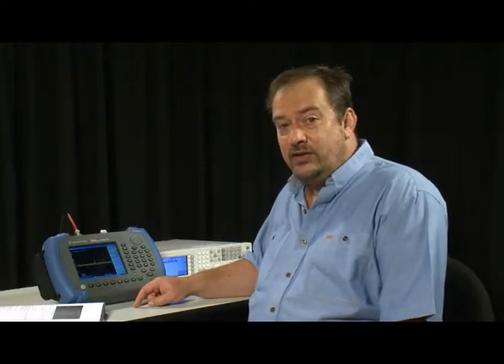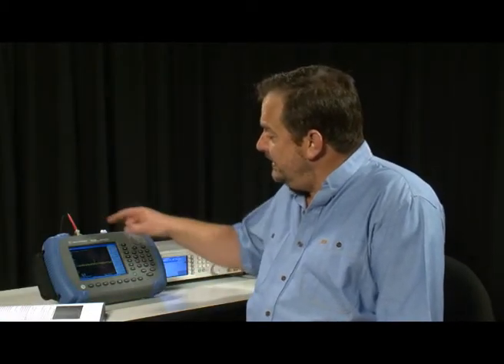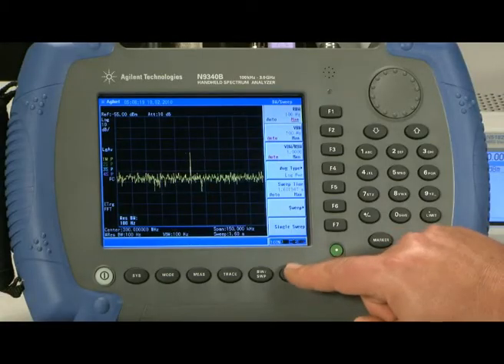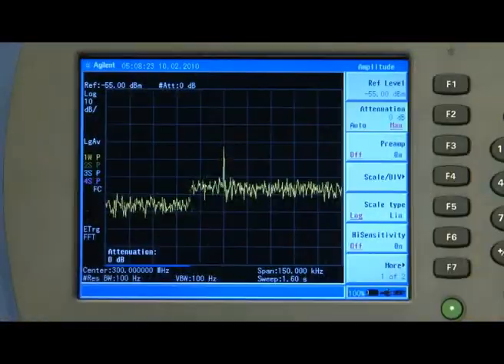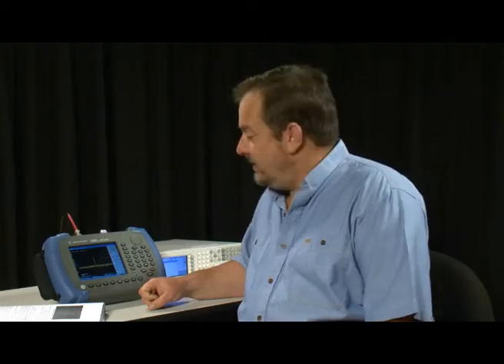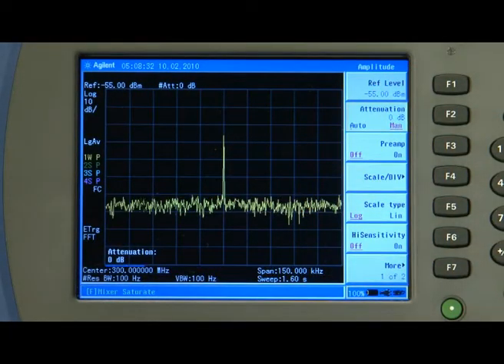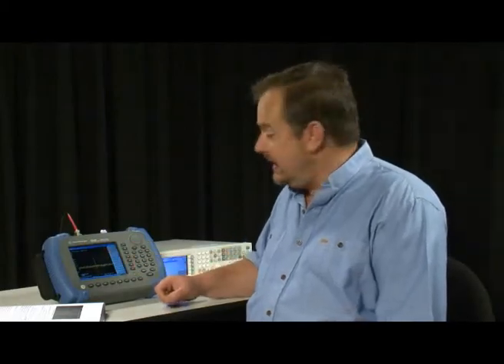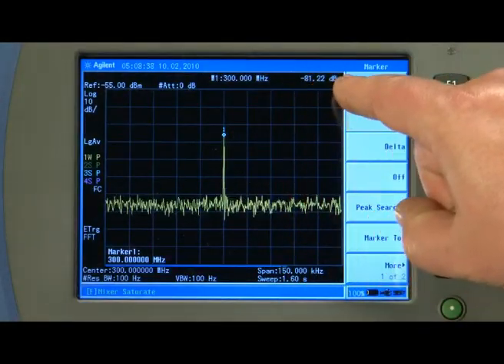Now there's one more thing we can do to improve the sensitivity still further and that's to remove all the attenuation in the input signal path. So I'll press the amplitude button, press the attenuation button and enter 0 dB. And as you can see that's given us roughly another 10 dB of sensitivity on the noise floor. And we can clearly see now the third harmonic signal from the signal generator. And if you want to measure the level of that, let's just press the marker button and we can read it off here, minus 81 dBm.